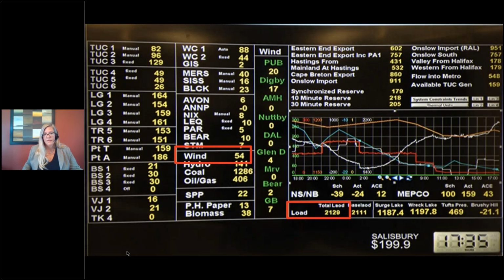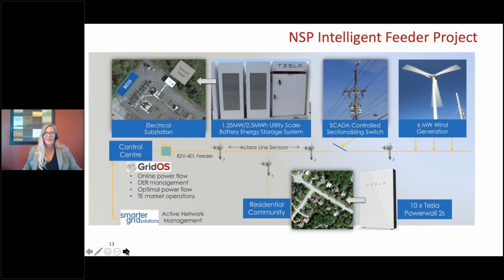Next slide. Enter the Intelligent Feeder project. We were approached by Opus One to be a demonstration location for them. They were developing their Grid OS software, and we were interested in piloting storage in combination with intermittent generation. So we developed a feeder-level microgrid that involved installing a Tesla power pack at a substation, along with some power walls at customers' homes on the same feeder. We have 6 megawatts of distributed wind on that feeder.